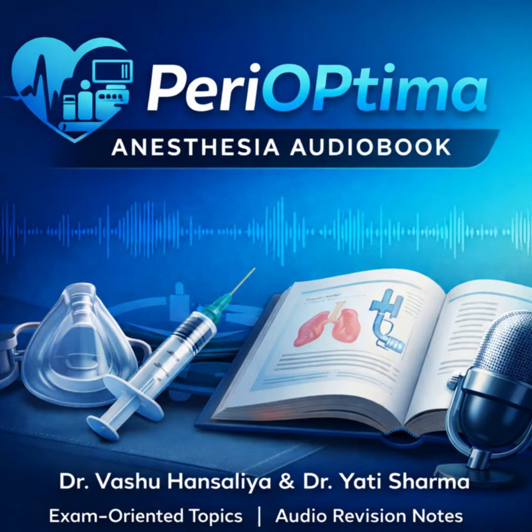The fresh gas inlet, or FGI. This is just where the mixed gases from the anesthetic machine enter the system. In a well-designed circle, the FGI should enter the circuit just before the inspiratory valve to make sure fresh gas doesn't bypass the patient. That level of detail, both chemical and mechanical, is exactly what's needed to secure full marks.